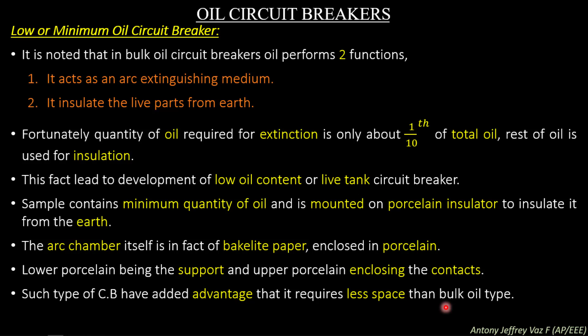The figure shows a minimum oil circuit breaker. You can see all the live parts of a minimum oil circuit breaker. At the top we have the oil level, and here are the terminals, and then we have a gas vent. This one is the upper porcelain insulation, and in this upper portion we have the fixed contacts, and in the lower end of the porcelain insulation we have the moving contact. The moving contact will be like a piston, so it will move upwards and connect the fixed contact. The complete circuit breaker is immersed in a minimum of oil. At the end you can see the drive crank, which is used to vertically move the moving contact towards the fixed contact, and at the bottom end there is a drain valve to drain the oil from the circuit breaker.